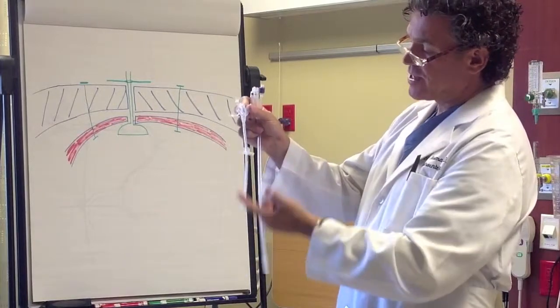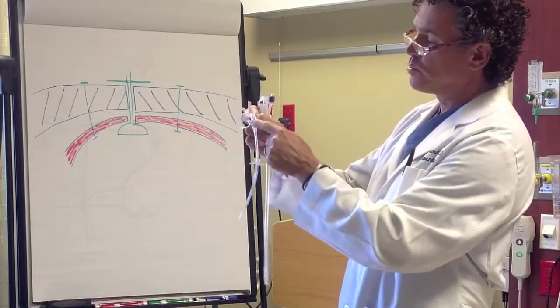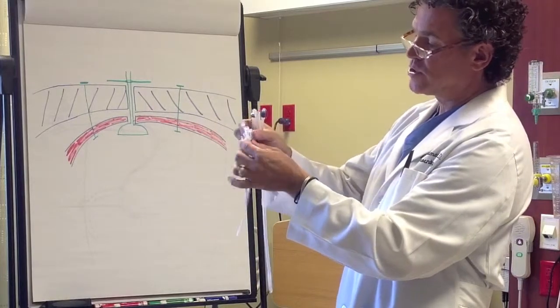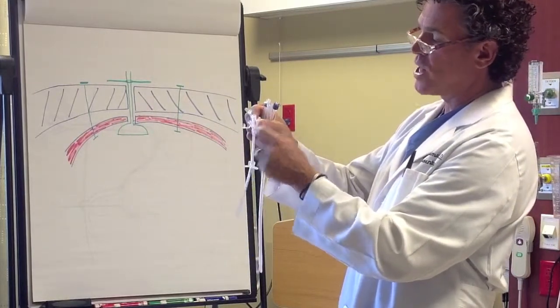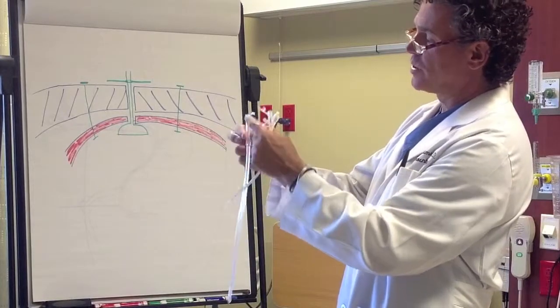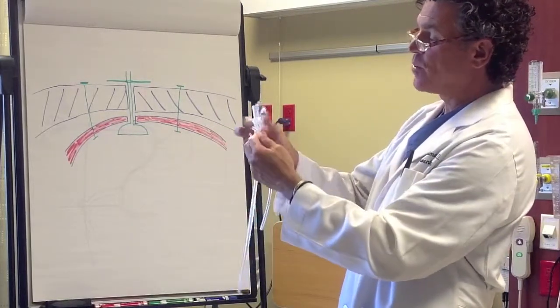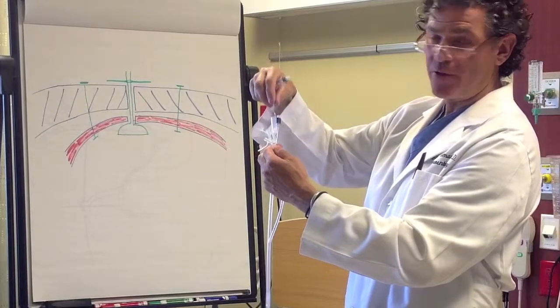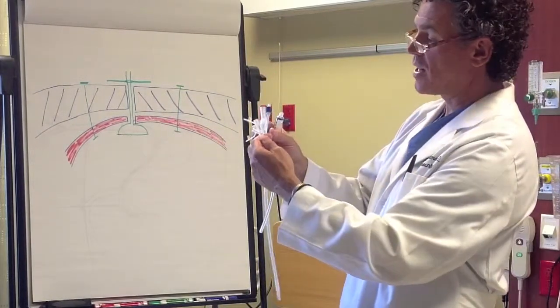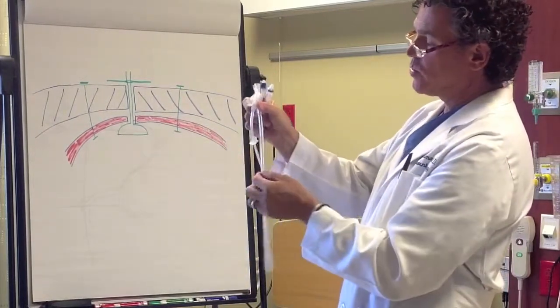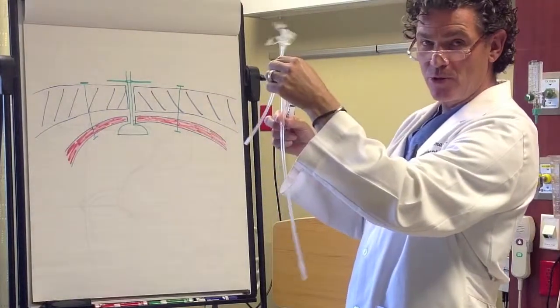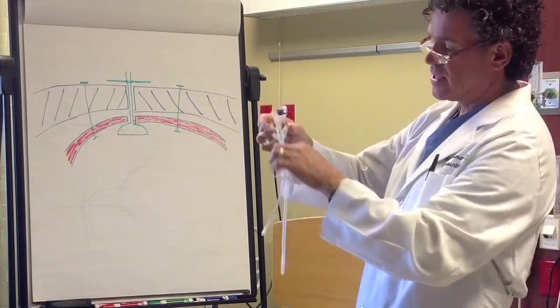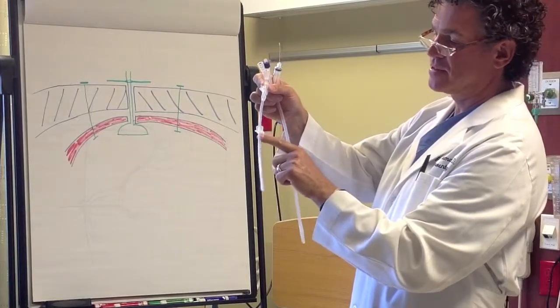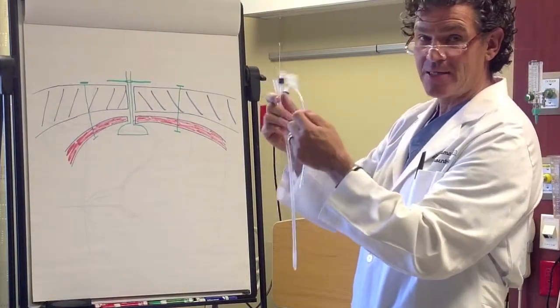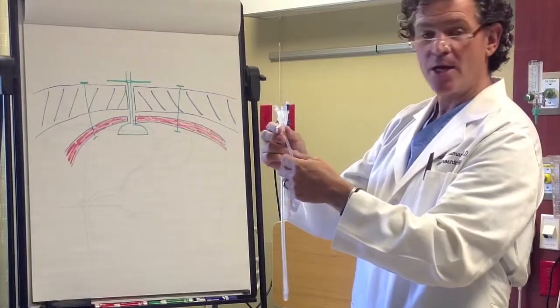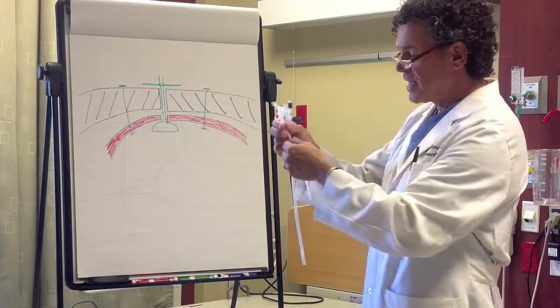This particular replacement gastrostomy tube has two little ports, one for a big syringe, a Toomey type syringe, one for a Luer-Lock type syringe, whereas the Foley catheter only has one for a Toomey, and we put our little stopcock adapters on there, our little stopcocks that have a Luer-Lock on it. But again, the only difference between a PEG replacement tube and a Foley catheter is the external fixation device.